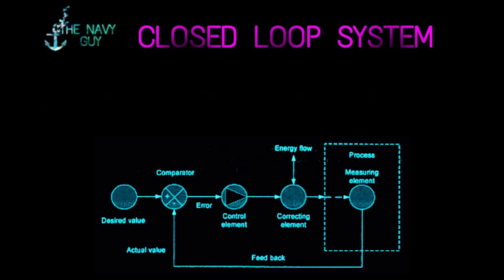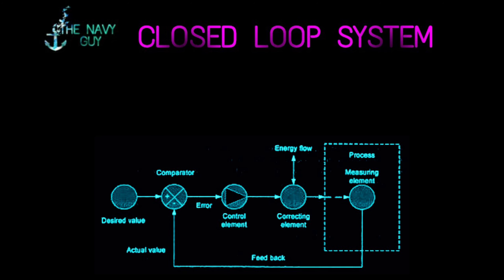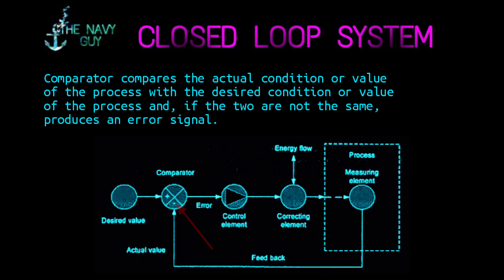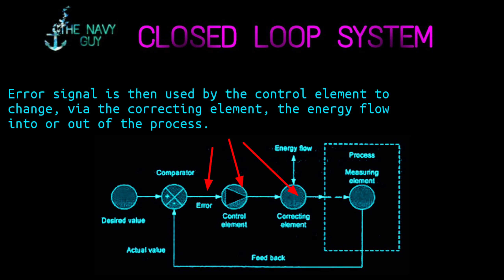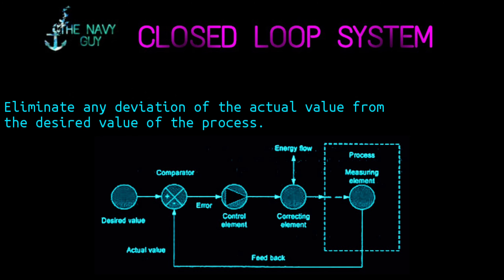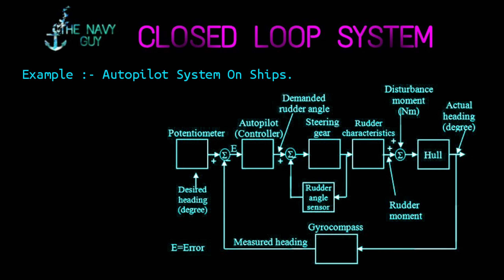In a closed loop control system, a sensing or measuring element is situated inside the feedback loop. The measuring element detects what is happening within the process and produces a feedback signal to a comparator, which reflects the actual value of the process. The comparator compares the actual condition with the desired condition, and if the two are not the same, produces an error signal. The error signal is then used by the control element to change, via the correcting element, the energy flow into or out of the process. This continuously attempts to eliminate any deviation of the actual value from the desired value. This system is potentially stable and very accurate. An example of a closed loop control system is the autopilot system on ships.